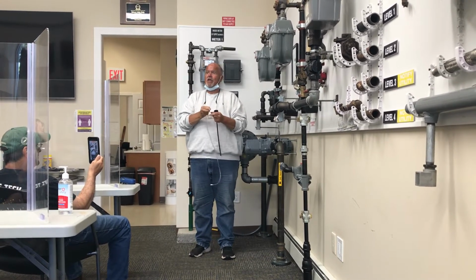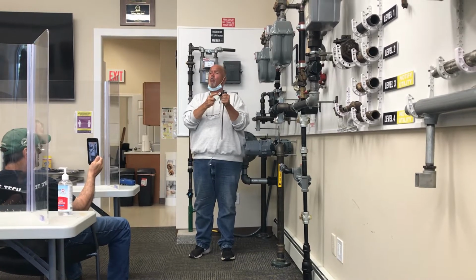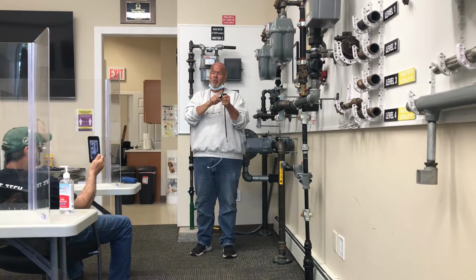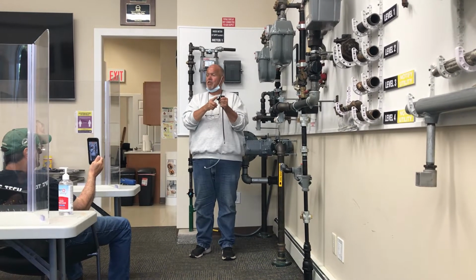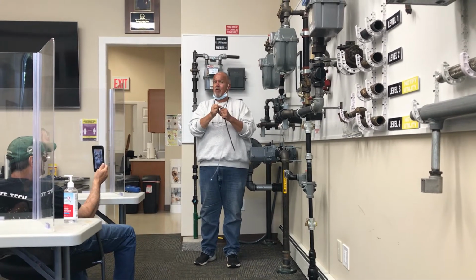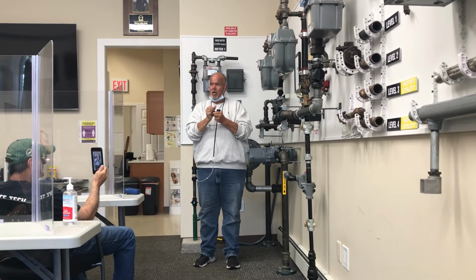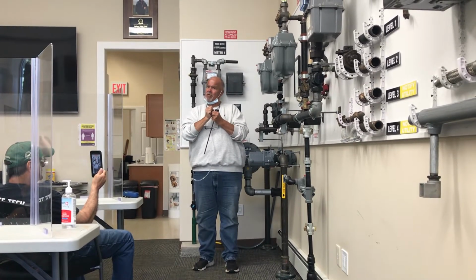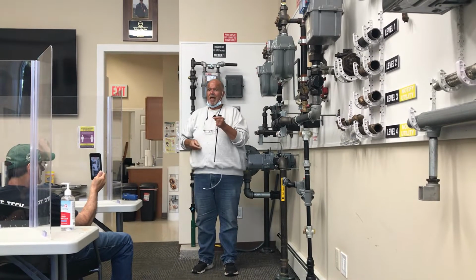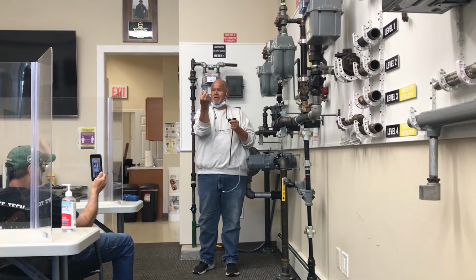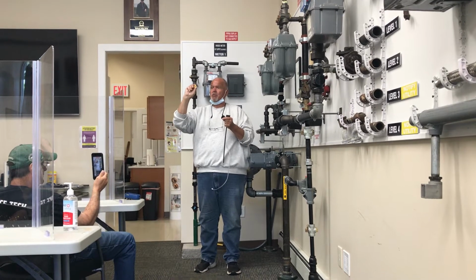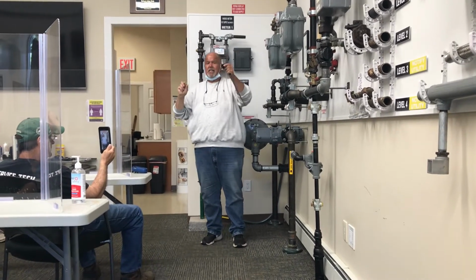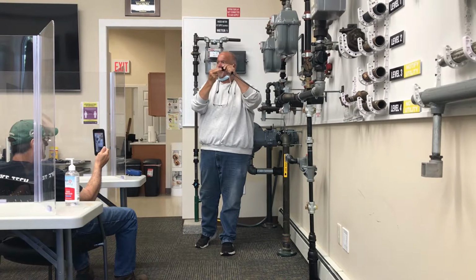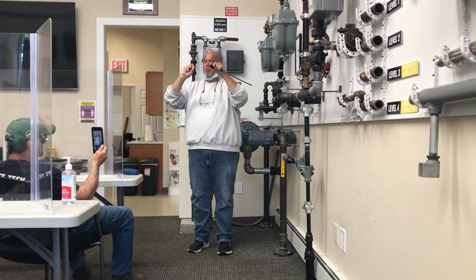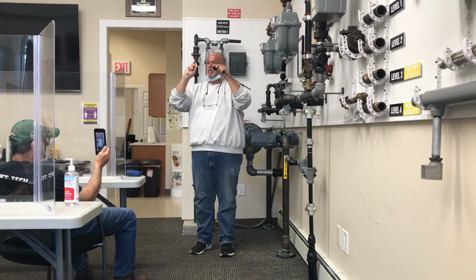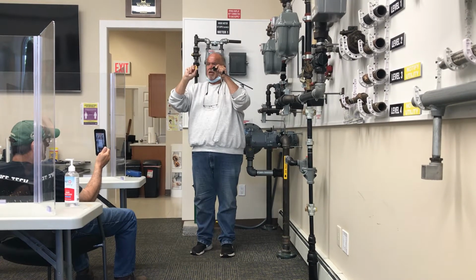Next, you want to check the hydrophobic or water-sensitive filter. The first one collects dust or solids. This one is designed for moisture, right? We don't want moisture to get into the machine. You want to pull out this filter, which is about the size of a nickel. You'll see it has a white side and a yellow side. The yellow side also has writing on it. Inside this cap is a yellow ring with writing on it also. Yellow is supposed to face yellow. If you're colorblind, it's writing faces writing. Yellow to yellow.